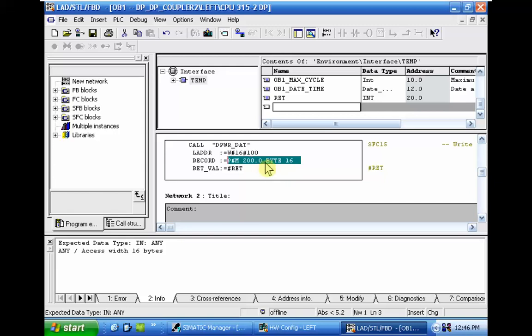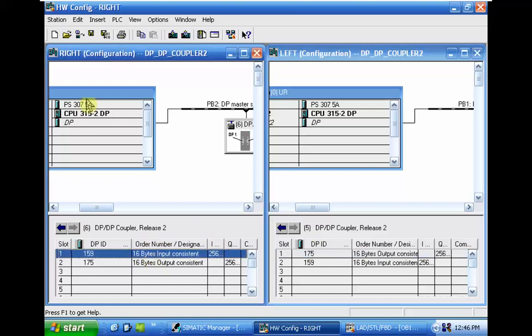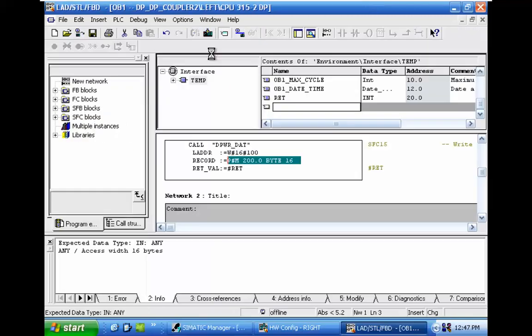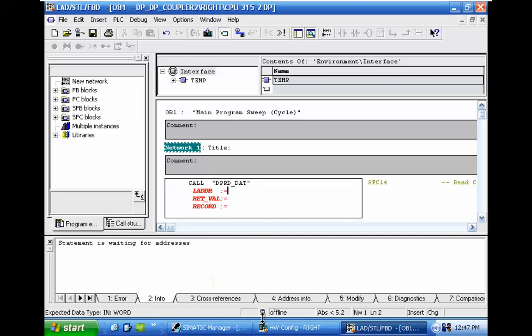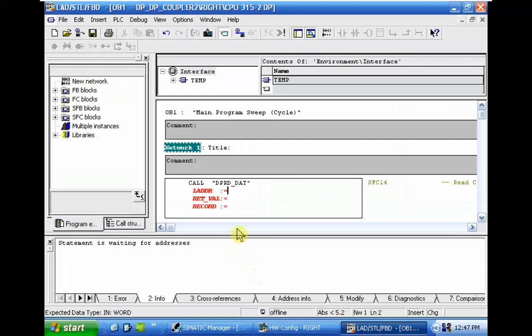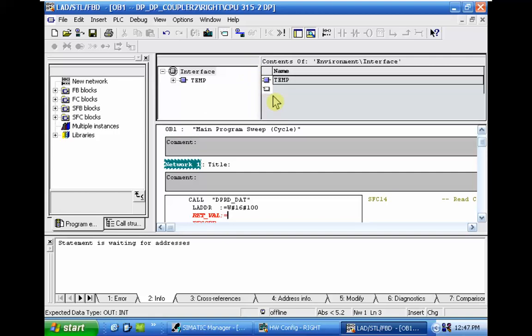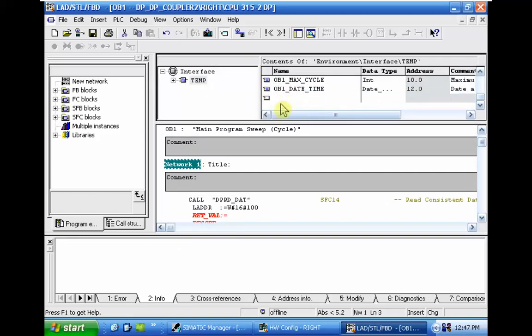To send data from the memory area, the starting memory area is M 200.0, 16 bytes from here. We will send data over SFC 15. We will send data from the output in a consistent manner and we will receive that in the right CPU using SFC 14. Call SFC 14, and the same L address, word 16 #100, return value, same integer read.